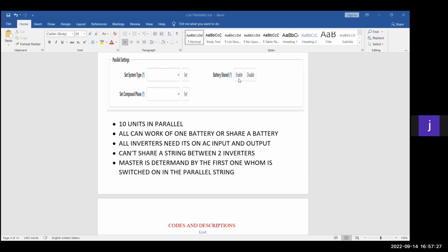But if it was a shared battery bank, you can use the maximum amount of capacity of your batteries, because then all three inverters will use that battery power, and all three inverters will charge this battery and all of that, if you can understand what I'm trying to say there. So battery shared is one of the functions that I always try to enable on my machines, always on one battery bank if it is possible.